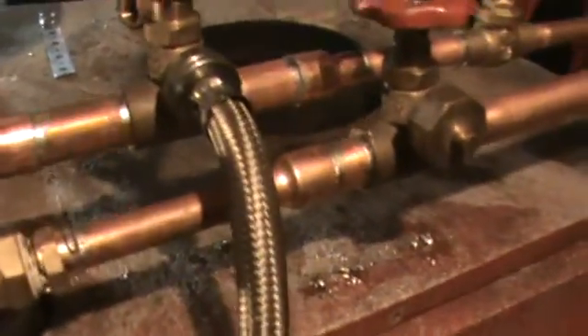All in all, it's got 25 pounds on her. All my work here — I don't seem to have one leak all the way through. Now it's leaking a little bit on the bottom of that pump; I snugged it up some, but again that's a rubber gasket and as the heat gets to it it'll probably seal better. A lot of that water on the floor is from filling — you have to keep letting the air out, and I used the pressure release valve to do that and water came out and poured all over the place.